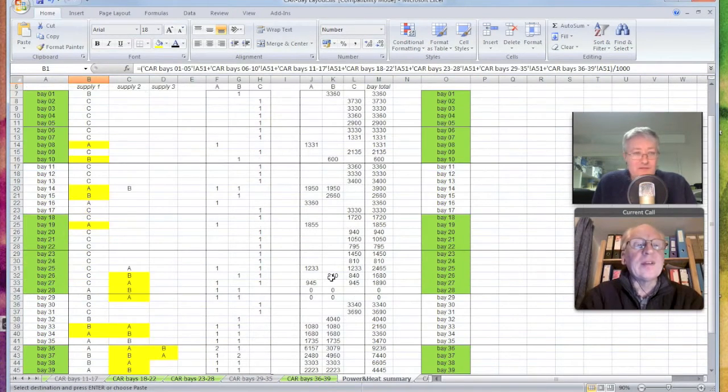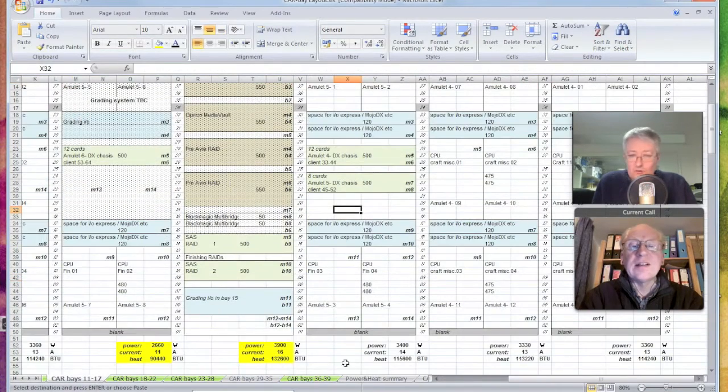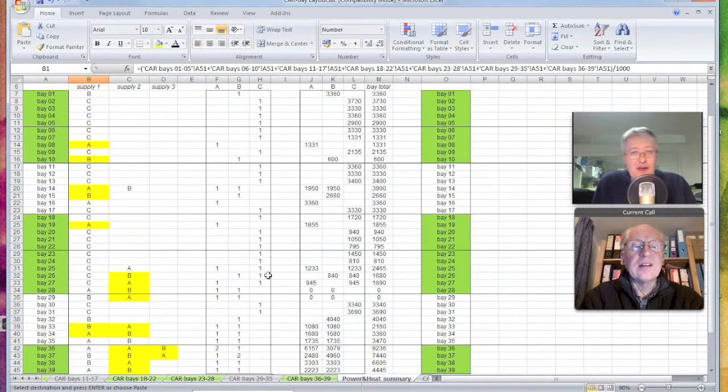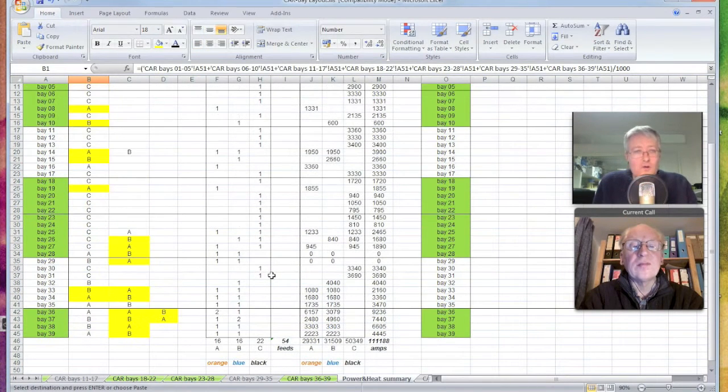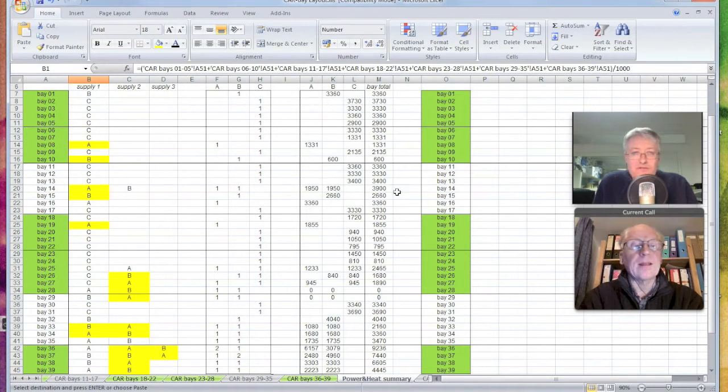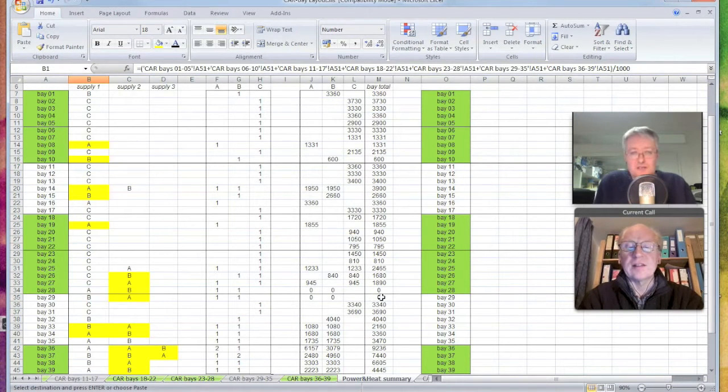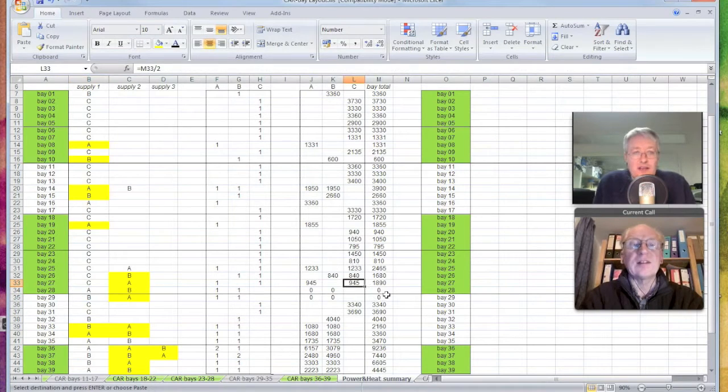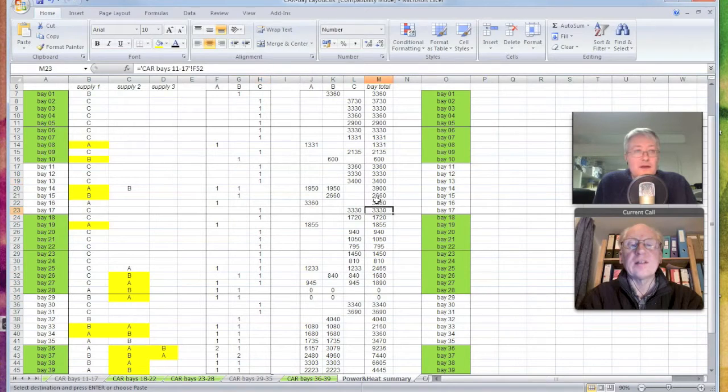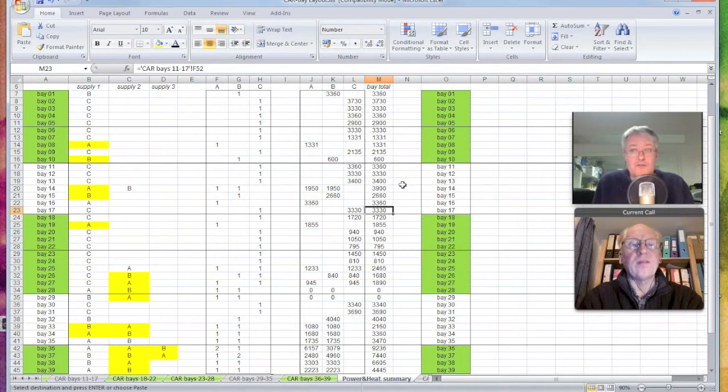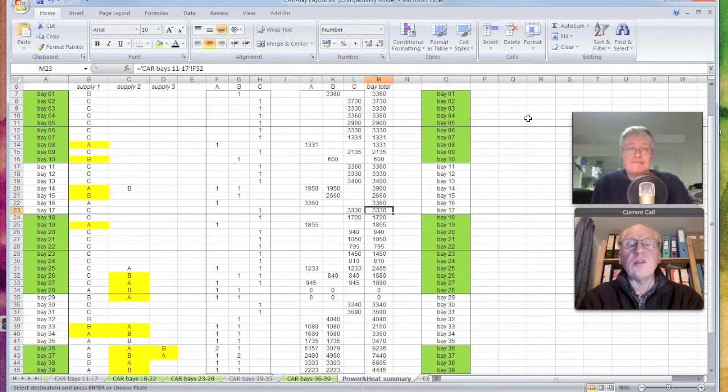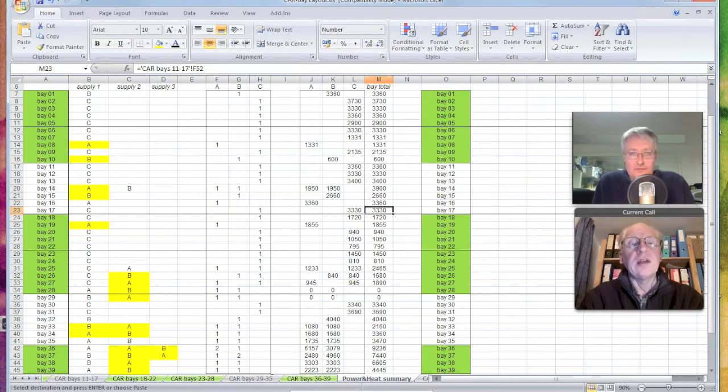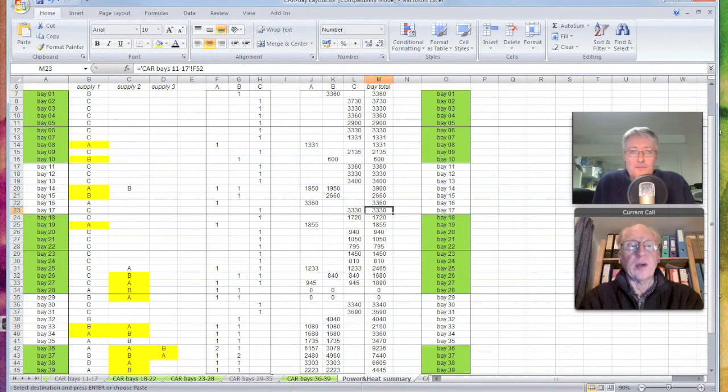But even the motors, even the rotation of the motors eventually gets turned into heat doesn't it. There's pretty much no energy that leaves a piece of broadcast equipment that doesn't leave it as heat in the end. So yeah I normally just tell the aircon guy, yeah we're consuming this many amps, it's going to be this much heat. And we're going to be within a percent of the real figure. And in fact if in the case of this job I've done all those calculations, I would then have a power and heat summary because quite often aircon guys like to know where the heat in the room is.